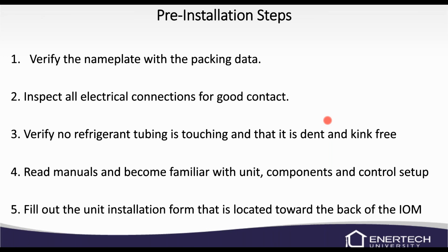Before you install the unit, make sure you've got the proper unit. It would be terrible if you hooked up a unit and realized, well, this is a 3.5 ton unit and I need a 5 ton unit. So just make sure we shipped you the right unit. Inspect all the electrical connections, even the factory installed connections. Sometimes terminal blocks can become loose during shipment, kind of rattle loose. So make sure those connections are tight and you've got good contact. Take a quick look at the refrigerant piping. Make sure the compressor is not falling over to the side or something like that, and that they haven't dropped the unit.